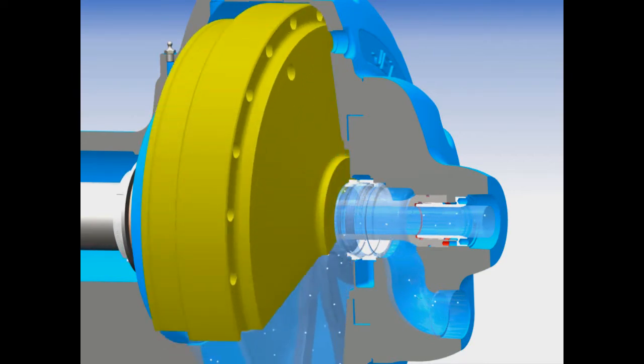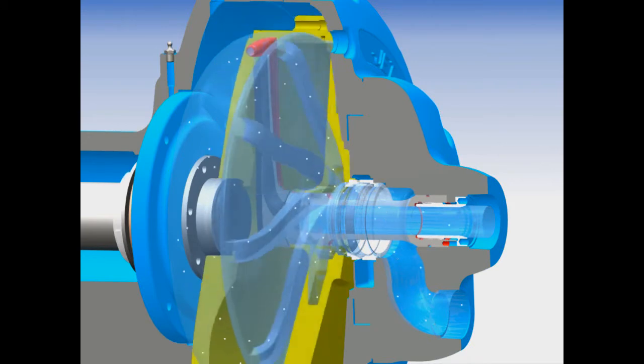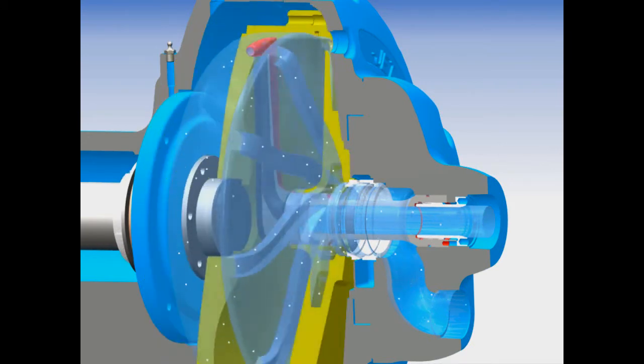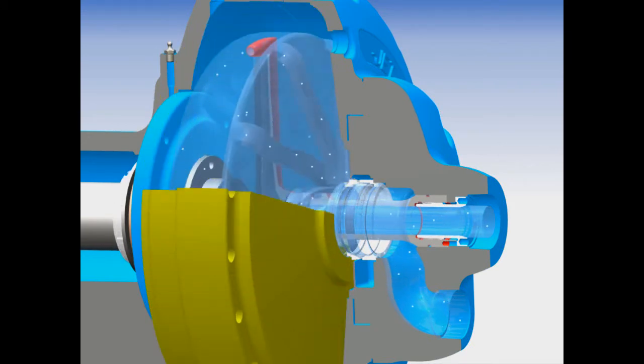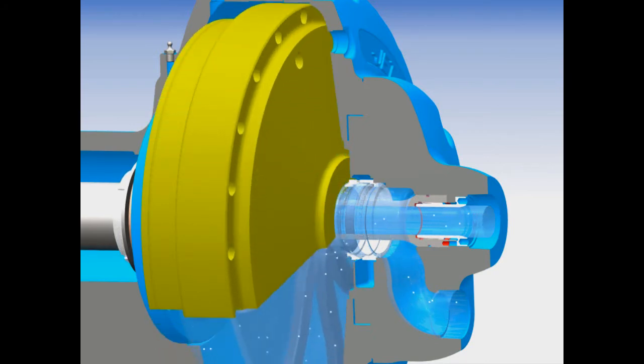The rotor jet has the ability to change pressure merely by adjusting the speed, the ability to change capacity by changing the pitot tube size, and the ability to purge itself of air on start-up.